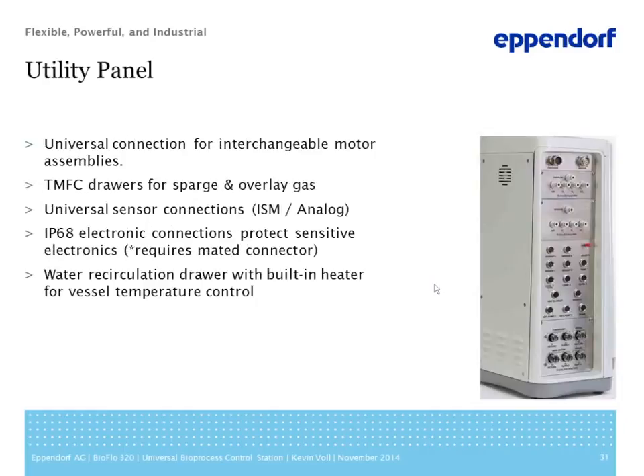The utility panel on the right-hand side shows all of the connections for your process control. So universal connections for the interchangeable motor assemblies are on the top. You can see where the drawers are inserted for the sparge and overlay gas, which is right below the motor connections. The universal sensor connections are within the electronics bank right here. That entire bank of electronic connectors is rated to IP68, so we've incorporated a very robust protection of the sensitive electronics using the ingress protection connectors.